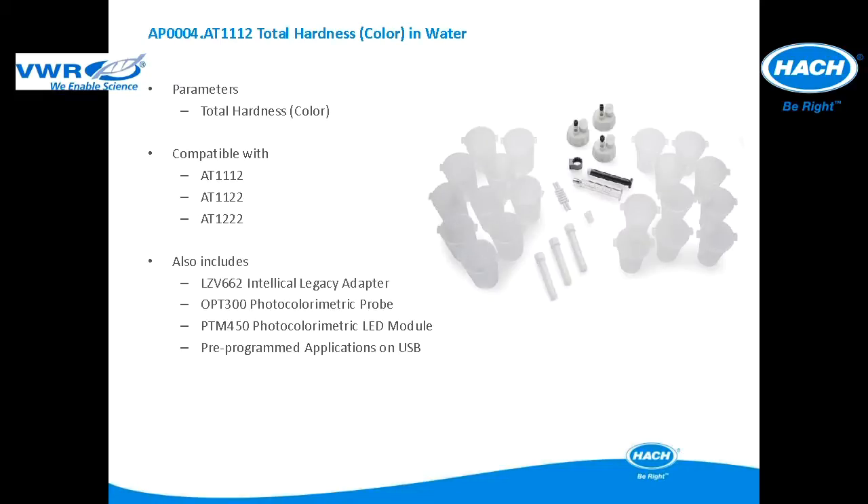This application package is a colorimetric titration method used for total hardness by the sum of calcium and magnesium hardness in water applications. The application package is compatible with the AT1112, AT1122, and AT1222. It includes all of the items pictured as well as the LZV662 IntelliCal Legacy Adapter, the OPT300 Photocolorimetric Probe and the PTM450 Photocolorimetric LED Module. The pre-programmed applications are included in a USB application key.